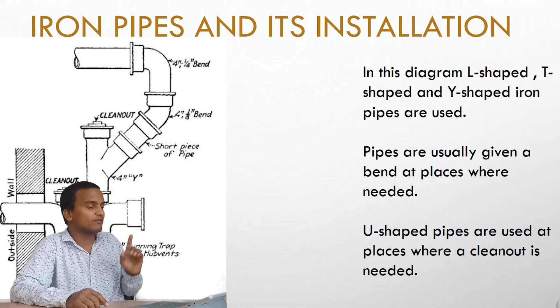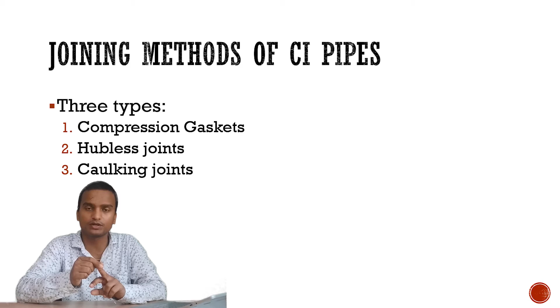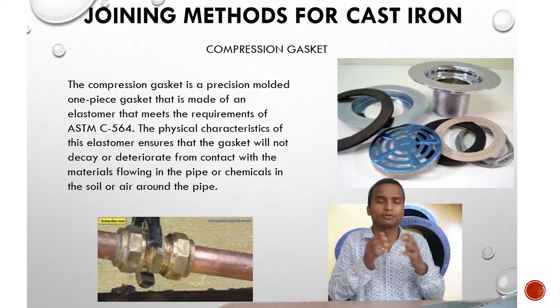What are the different joining methods of cast iron pipes? There are 3 methods of joining cast iron pipes. The first one is compression gaskets, the second one is hubless joint, and the third one is caulking joint. A compression gasket connects 2 pipes of maybe different diameter, different capacity, and this one-piece compression gasket is made of a material called elastomer, which meets the requirement of not easily decaying or deteriorating from the materials flowing inside the pipe, or material present in the soil if the pipe is laid beneath the soil, or the material in the air.